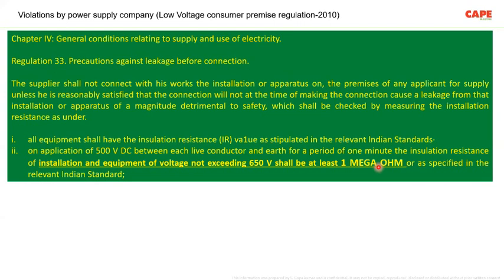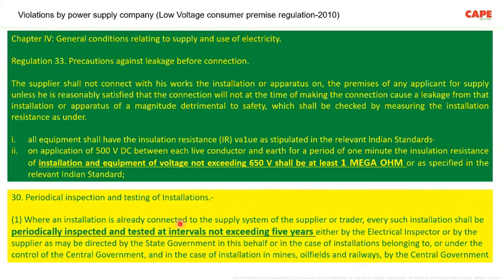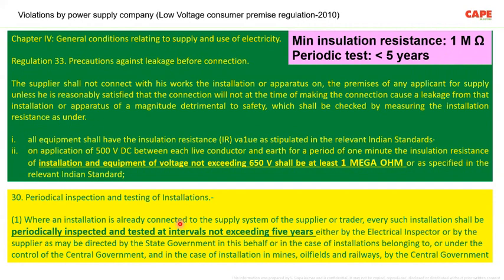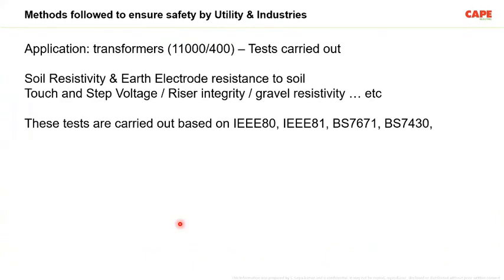Somebody asked a question just before on the chat box, which I just answered in the Q&A. While testing, the gentleman has got about 2,150 mega ohm. Whether this is sufficient or not? Yes, of course, more than 1 mega ohm is accepted. Now, periodic inspection by the utility every 5 years is also recommended in the regulation. Of course, these are also not followed properly. If these regulations are followed properly, a lot of accidents can be stopped, because the mistakes can be caught well in advance.